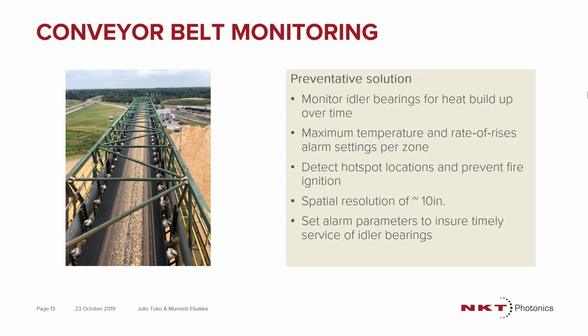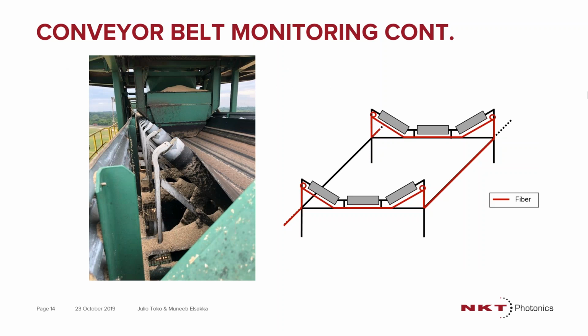So essentially, you still have the same spatial resolution of about 10 inches, which is industry standard in fiber optics. And you can detect very precisely where along your conveyor system you have unwanted heat. This is just a typical layout of what a design and routing for the fiber optic cable would look like. You pretty much would trace the idler bearings underneath the belt, and you monitor heat along these idler bearings, and you take a proactive approach to maintenance of your conveyor system.